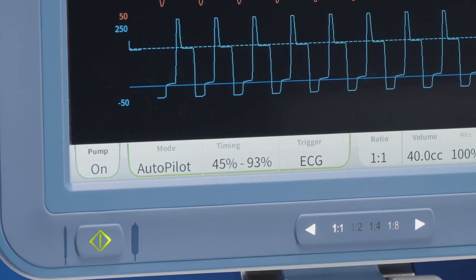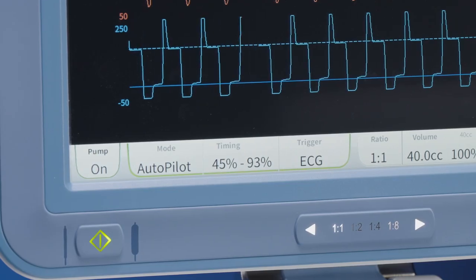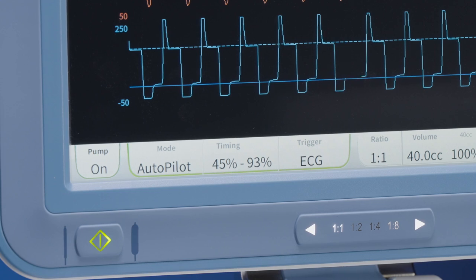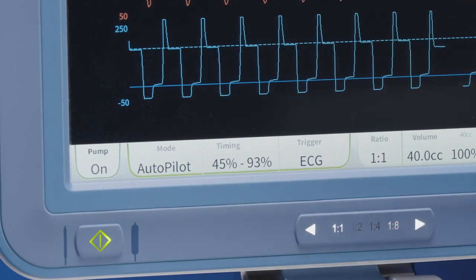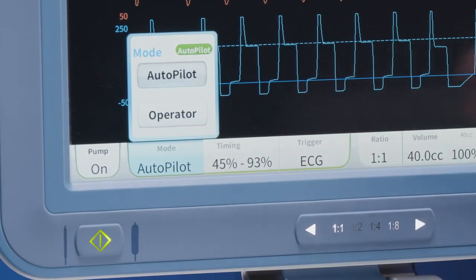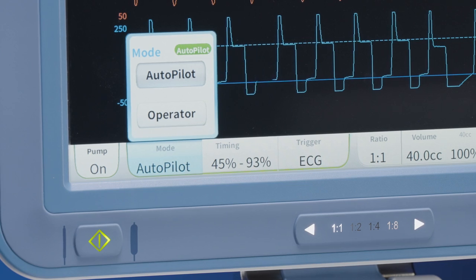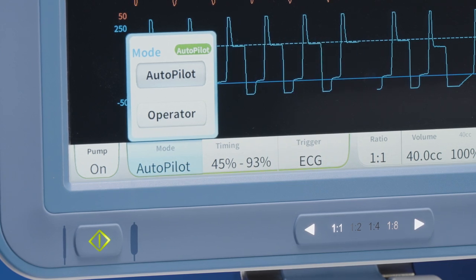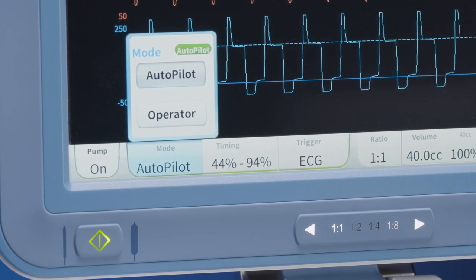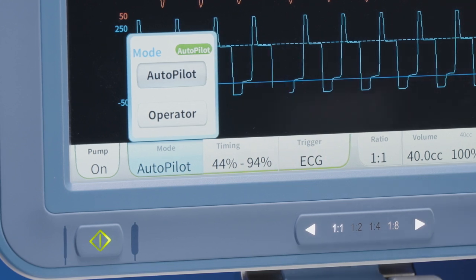The mode of operations. The AC3 Optimus IABP has two modes of operation, autopilot mode and operator mode. The default is autopilot mode. In autopilot mode, the pump selects the appropriate trigger mode, timing method, and settings automatically. The timing controls display but do not operate.